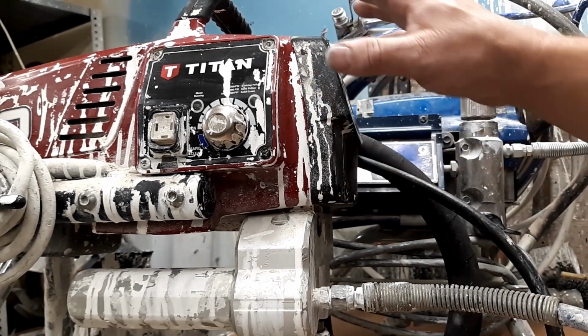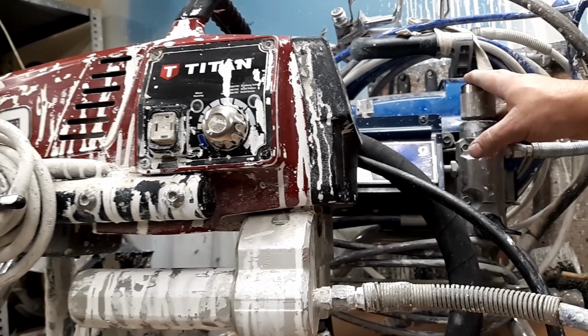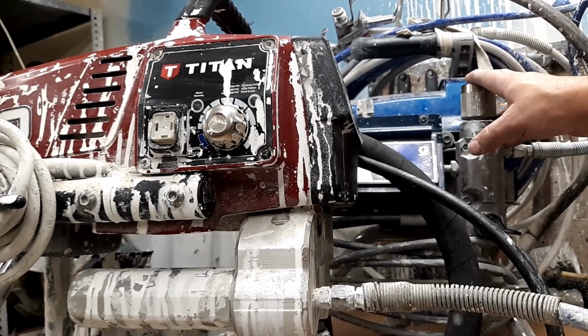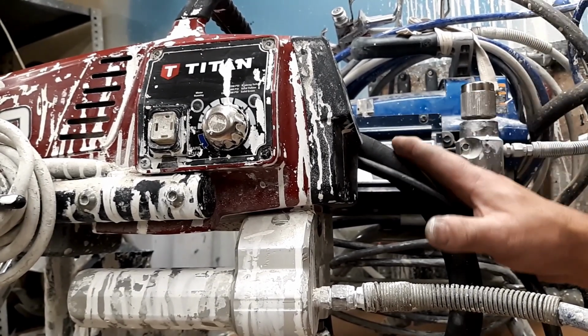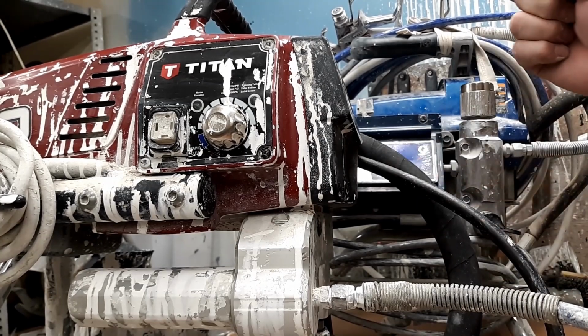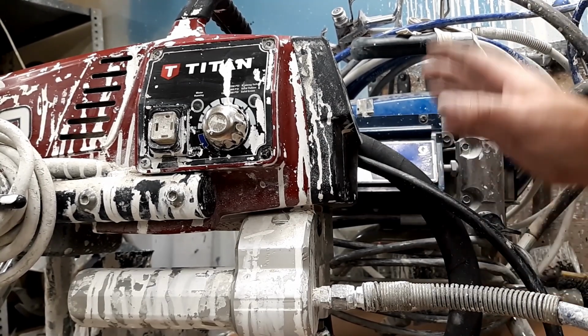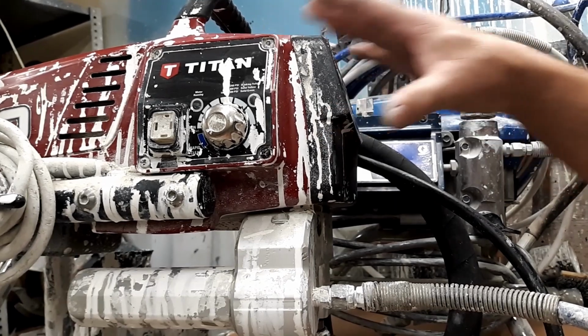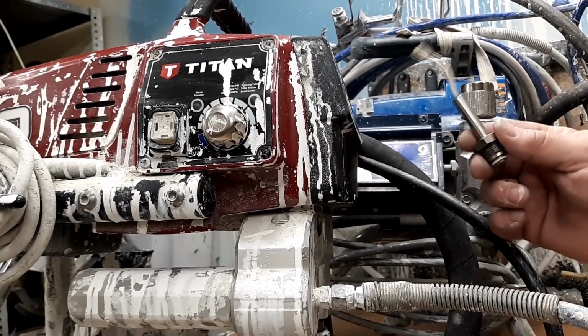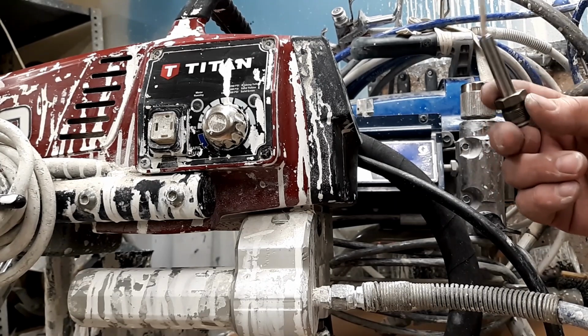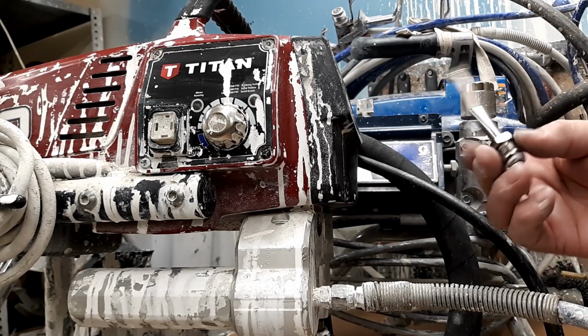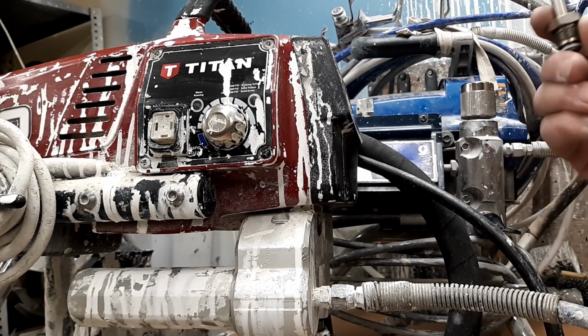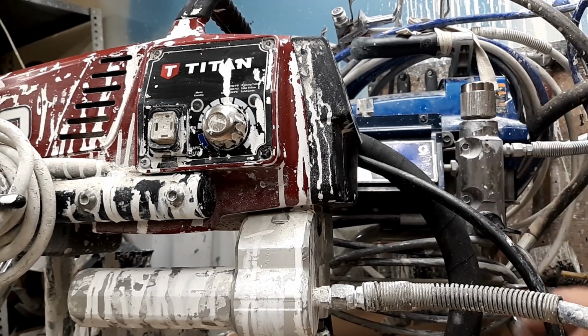The second thing is going to be, after you find out the machine has frozen, check the transducer by turning the machines on to see if they run. If they run, you're not necessarily out of the woods. You're going to check your pressure. If your pressure gets exceedingly high, then you know the transducer. Conversely, if you turn it on and nothing is running, then more than likely the transducer itself is bad, and that's going to be the first thing you look at. And just look for my videos on my channel, because they're on there in regards to this replacement as well.